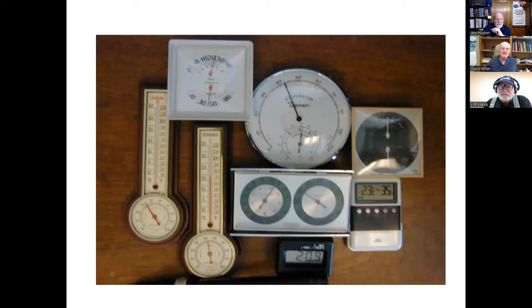In thinking about humidity, I've always admired this slide from a colleague retired from Canada Mortgage and Housing, Ken Roy, who went out one day and bought a whole bunch of hygrometers. As you can see, it's slightly out of focus, at the local hardware store. And you don't need the computer or even to have a sharp image to see that they're all over the place. So we try to tell people, including in non-industrial workplaces, but in their homes, to try to keep it between 40-50%, for a bunch of reasons. And yet this is what they mostly have to work with. So I thought about that as well.